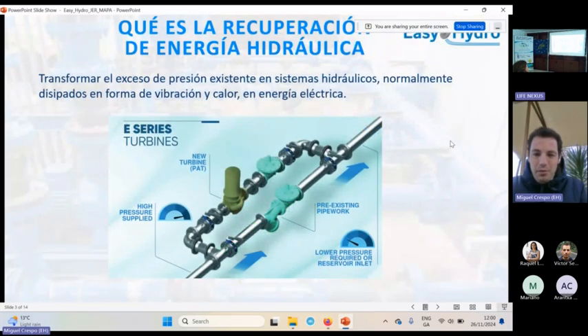A typical scheme of a hydropower energy recovery system. Well, what is a hydropower energy recovery system? So basically, it just transforms the excess pressure in water pipes into electricity instead of dissipating it in terms of noise, vibration, and heat. So in the typical scheme, and this is also always mandatory, it must be installed in parallel to a pre-existing, let's say, pressure drop system.